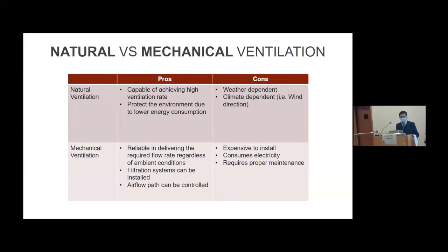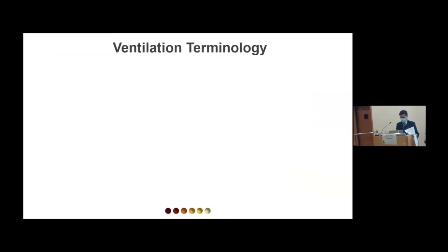Mechanical ventilation is much more reliable in delivering the required airflow rate regardless of the ambient conditions. Also, air purification systems can be installed in ductworks to control the indoor air quality, and airflow path can be controlled by designing the system with high and low pressure zones. The drawback of mechanical ventilation is that it has high initial installation costs, the fans consume electricity, and the equipment and air ductwork need space and require proper maintenance. Today's presentation will mainly focus on mechanical ventilation, which can be controlled by humans.